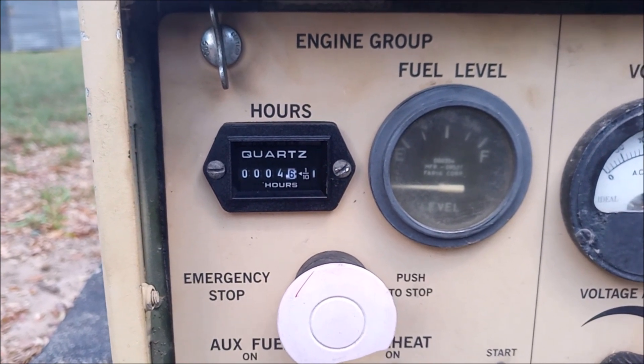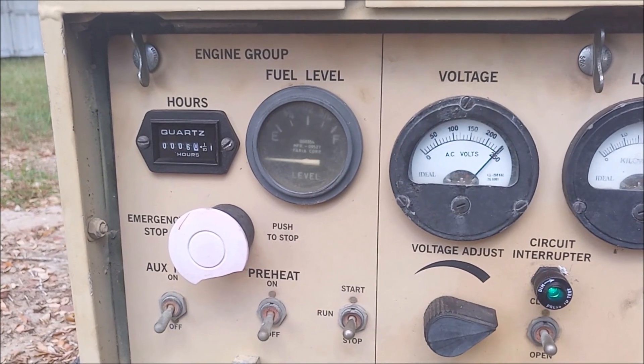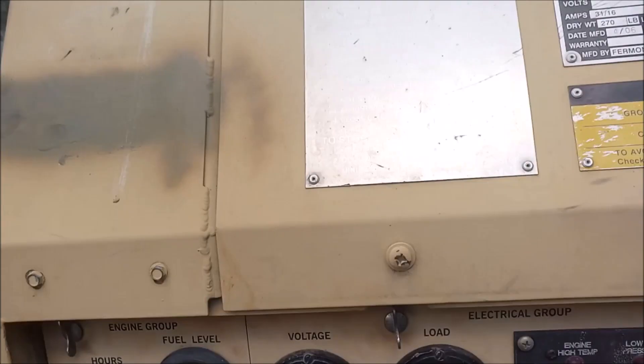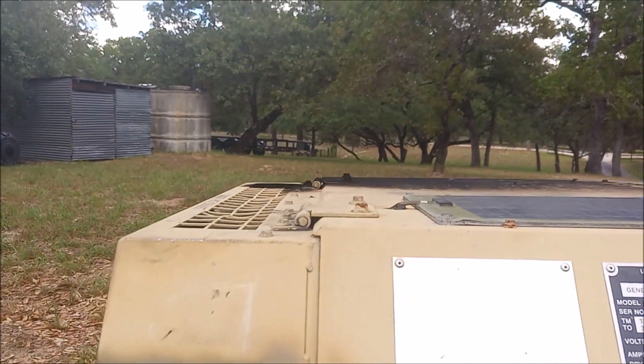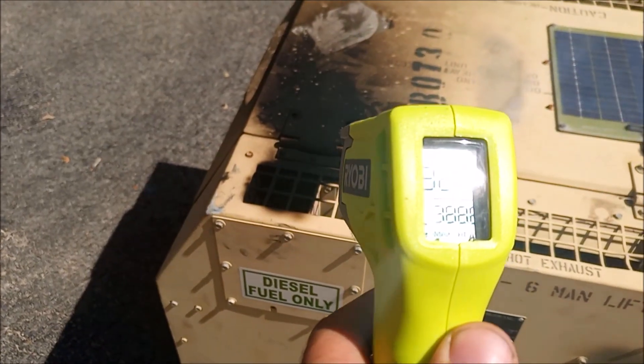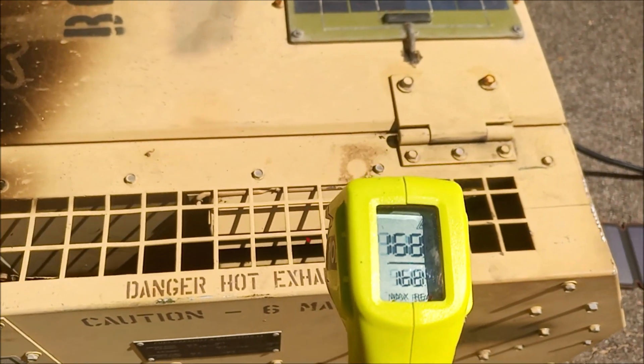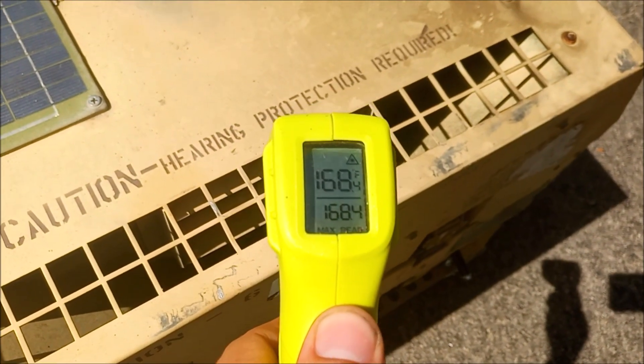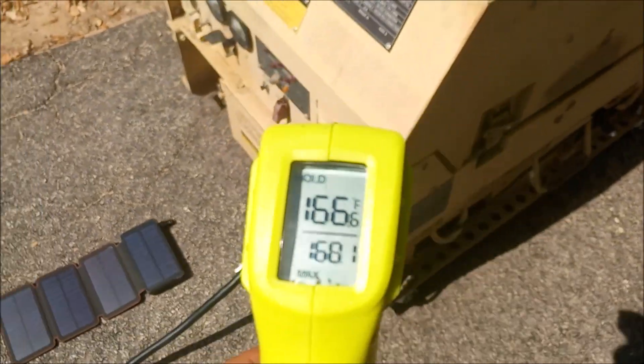It's been running for 3.6 hours, still no problem. Just rolled over to 5 hours continuous running at full load — no errors, no hiccups. It's definitely smoothed out a little bit, because before it was spewing a little smoke, which I expected. When it's really cleaned up, you just kind of get the heat barrage coming off of it, which is expected. That's the exhaust temperature there, that's coming out of the fan up here, and it's coming out of the fan on this side. That's the enclosure itself — you can see it in the shade.